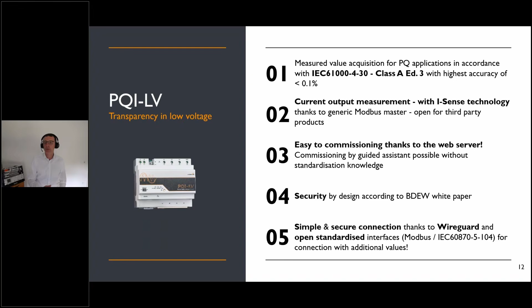The device can measure up to 4 voltage inputs, L1, L2, L3, neutral, as well as 4 current sensor inputs. For the current sensor inputs we have two options: very easy installation via Rogowski coils, or via 350 millivolt input signals. So the new and cheap technology for measuring current is not 5 amp or 1 amp, but a millivolt signal.